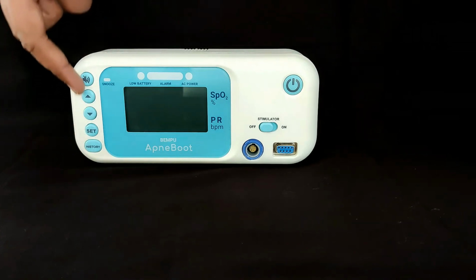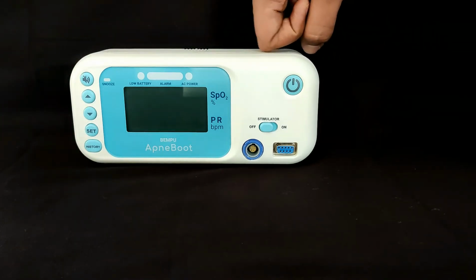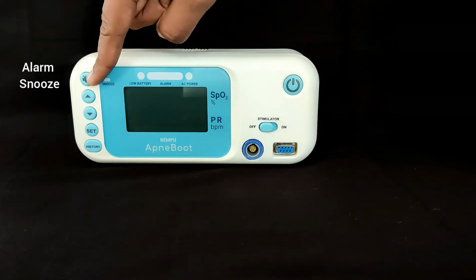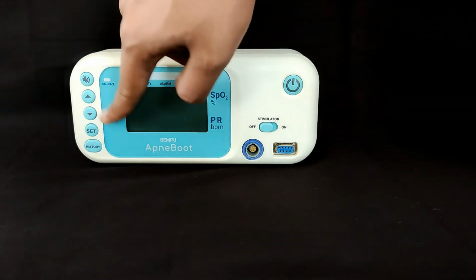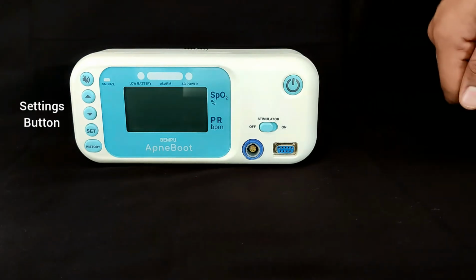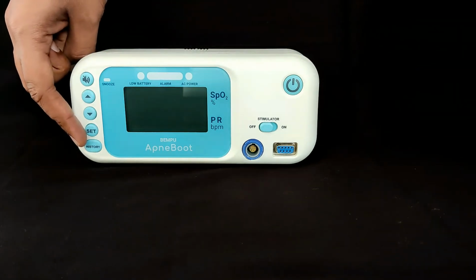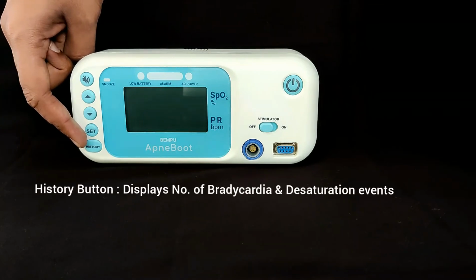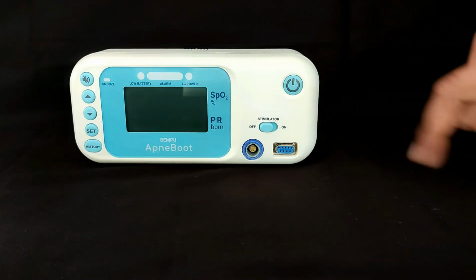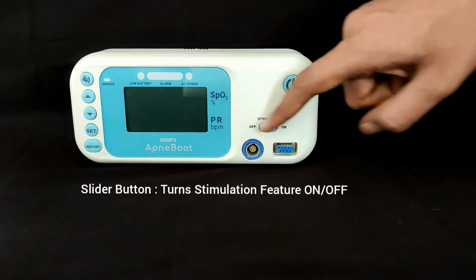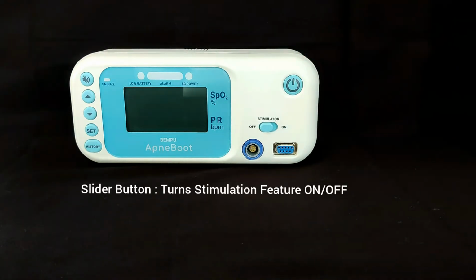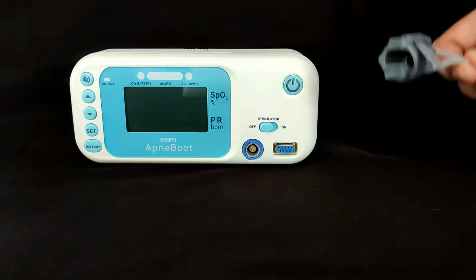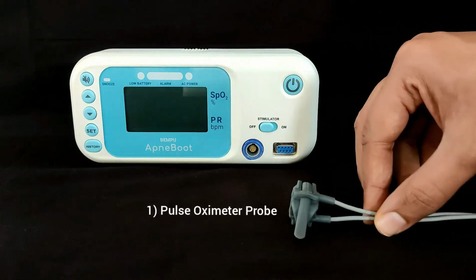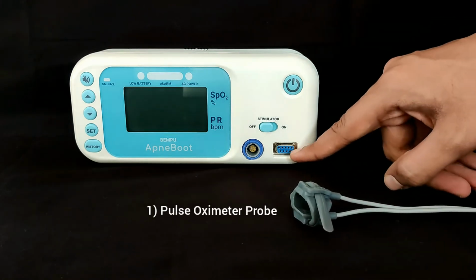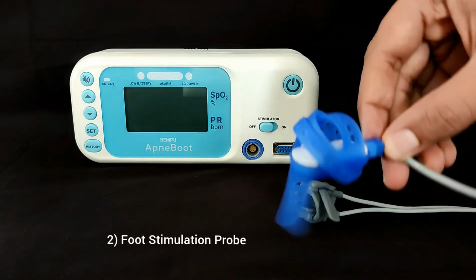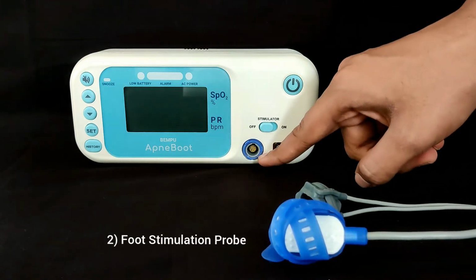Then there are these 5 buttons used to customize the settings of the device as needed. The topmost button is to snooze the alarm. The arrow and set buttons are to customize the device settings. And the history button is to display the number of bradycardia and desaturation events in the past 12 hours. The slider switch is to turn the stimulation feature on or off as needed. The device uses 2 probes. First, the pulse oximeter probe, which gets plugged in this connector. Second is the foot stimulation probe, which gets connected in the adjacent connector.